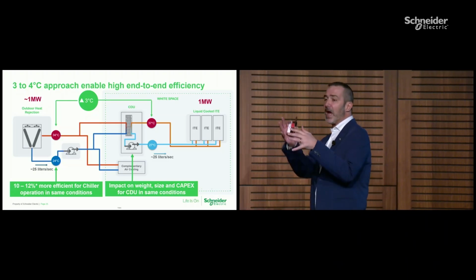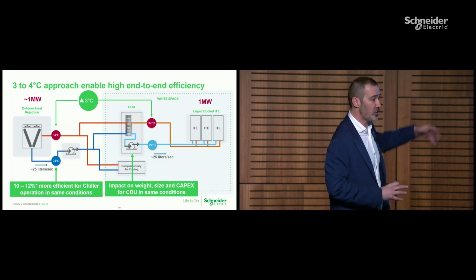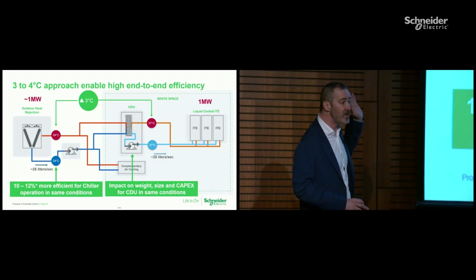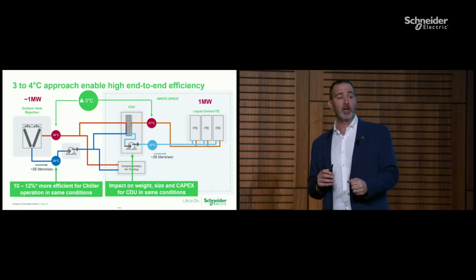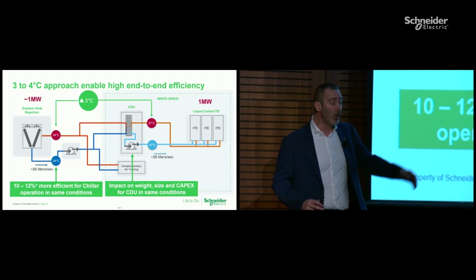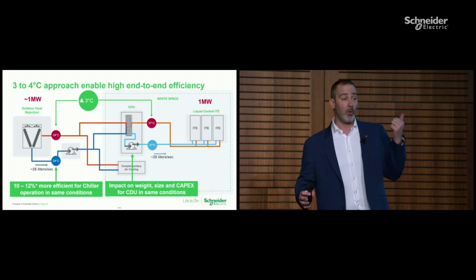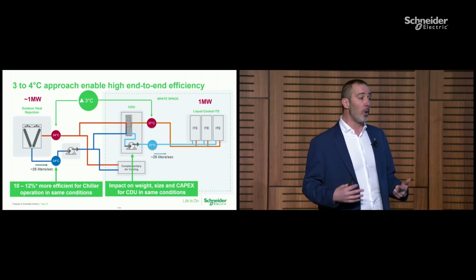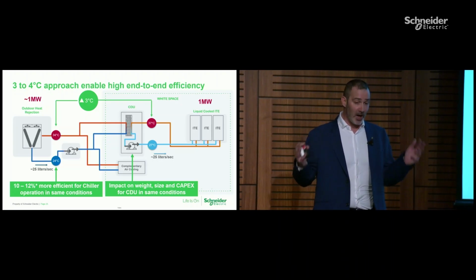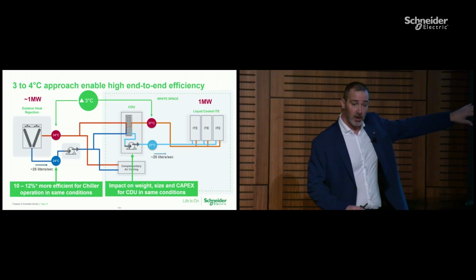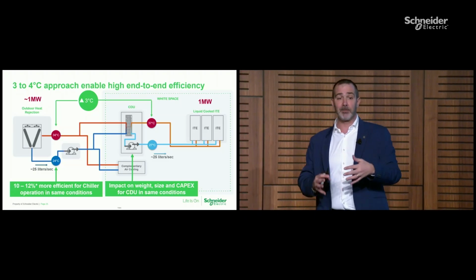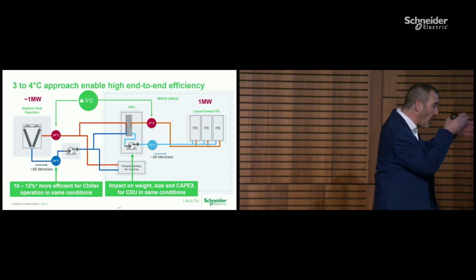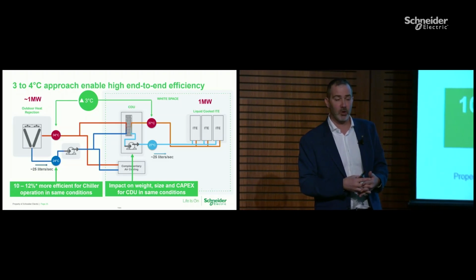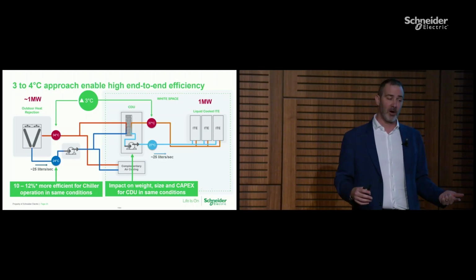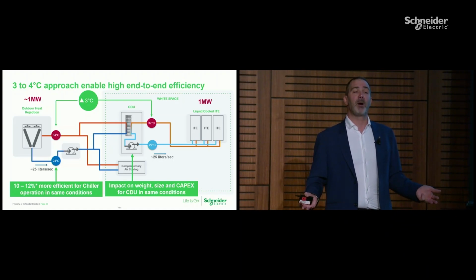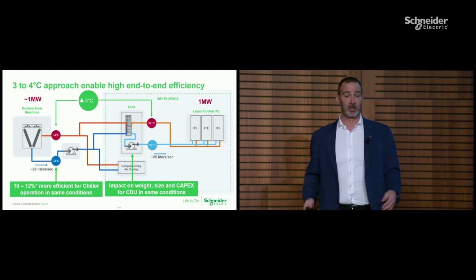And the real driver, the real big elephant in the room, when you look at the efficiency level, is the heat rejection unit. And every single degree Celsius you can raise the temperature at the chiller, you get 3% more or less in efficiency. So it is true that a CDU with a very low approach is probably and likely more expensive. The CDU needs a larger pump, so power consumption is much higher, and the unit is heavier and larger. However, accepting that, the full end-to-end architecture is 10-15% more efficient. So again, if you look at only a small portion, only the CDU, why would we select a very small approach CDU? It is more expensive, heavier, larger, and has more power consumption. But when you look at the end-to-end approach, that's completely different.